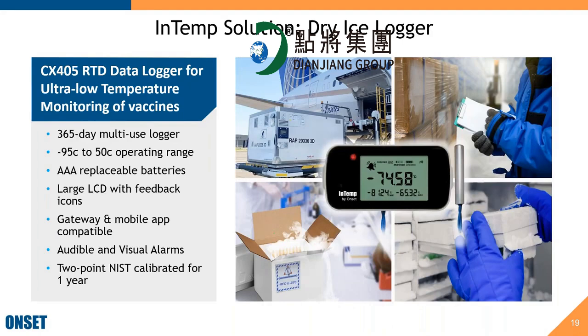We have an LCD version of the dry ice logger. We built this specifically for COVID vaccines. So back when those vaccines were being kept in dry ice conditions, we were listening to our customers and to the regulatory bodies who were all saying that they really needed that LCD. So we took our existing dry ice and combined it with our 400 loggers so that you have that display. AAA replaceable batteries, and it has audible and visual alarms. And again, 1 year NIST calibration, this one with 2 points.